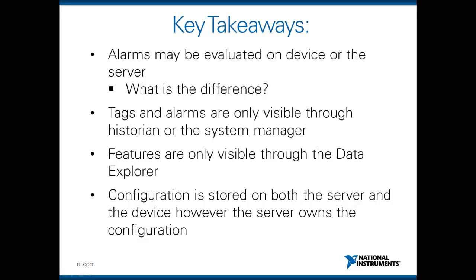What this means is that we have local copies of the configuration on each individual cRIO. This is important because if a cRIO boots up and doesn't have a network connection, he still needs configuration so that he can start acquiring data. We didn't want to make network connectivity a prerequisite for data collection. So he does have a copy of configuration stored locally.